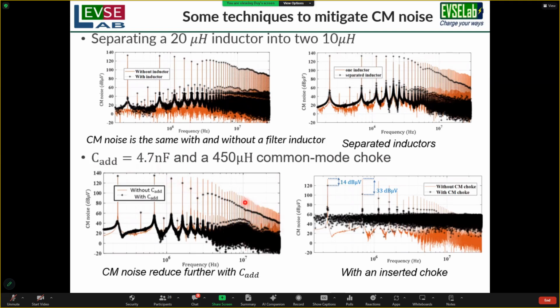If we still don't accept this noise level, we can add a common mode choke of 450 microhenry. Then the noise can be reduced starting from the first harmonic order, reaching more than 30 decibel-microvolts reduction in the high frequency band of the common mode noise.